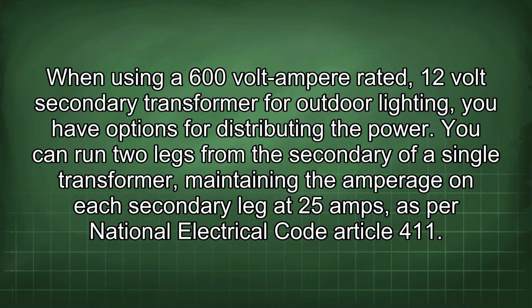When using a 600-volt ampere-rated 12-volt secondary transformer for outdoor lighting, you have options for distributing the power. You can run 2 legs from the secondary of a single transformer, maintaining the amperage on each secondary leg at 25 amps, as per National Electrical Code Article 411.